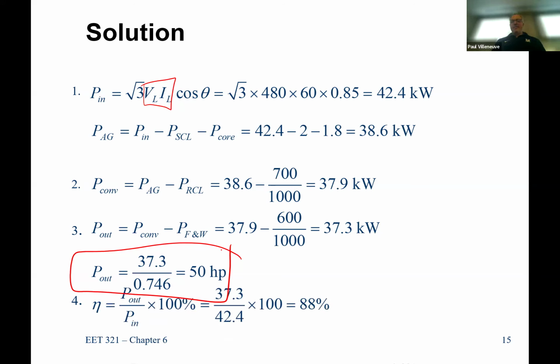And then finally, the efficiency of this machine, P out over P in. I put out 37.3. This is mechanical torque. My input was 42.4, 88% efficient, which I would call average efficiency for an induction machine. Doesn't have to be elegant, just average typical efficiency.